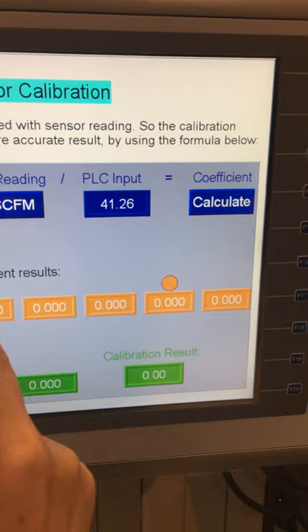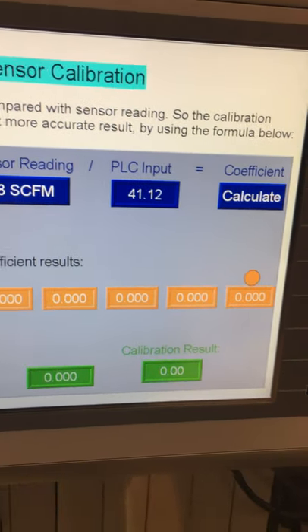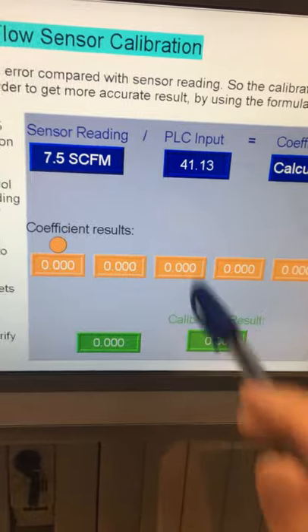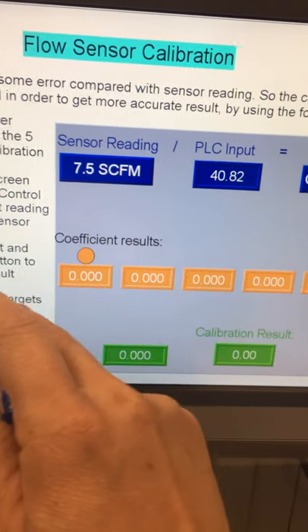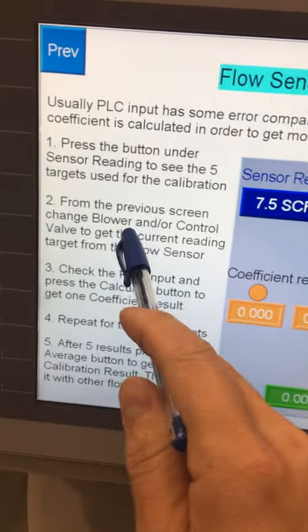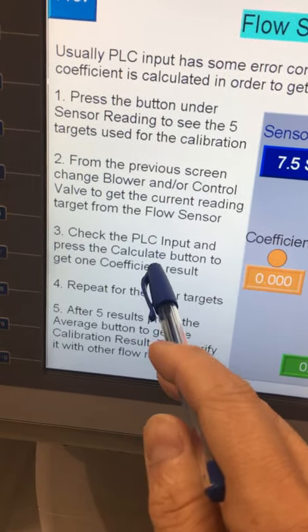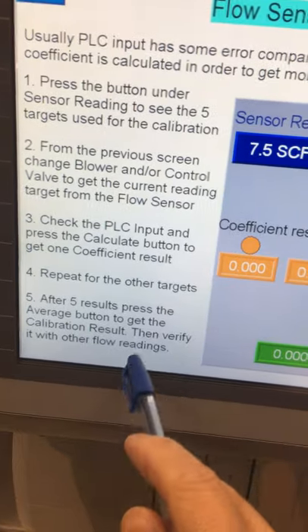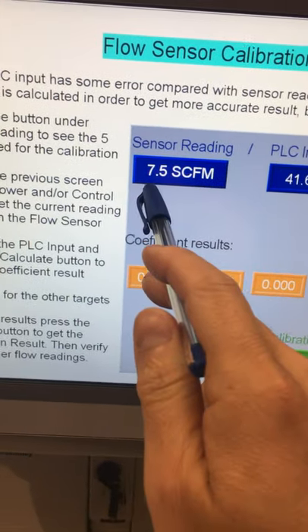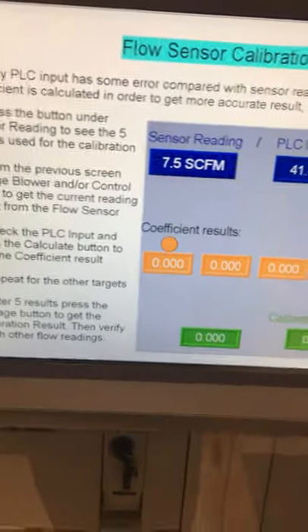Of course, you need to make the real change on the device in order to get the accurate reading. So let's do it on the first one. We need to use the previous screen to change the blower or the valve, then check the PLC and press the button. I'm going to show you the whole process. Right now we're trying to get a 7.5 reading on the flow sensor. Let's look at what we have right now. It's 42 point something, it's too high, because the blower is working at 100%. So we need to go to the previous screen.